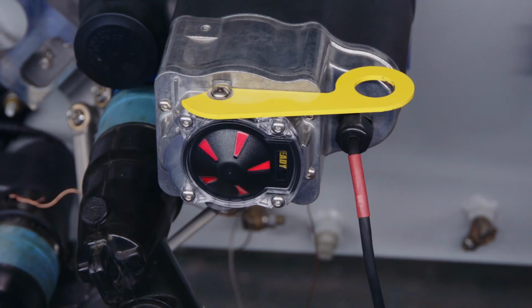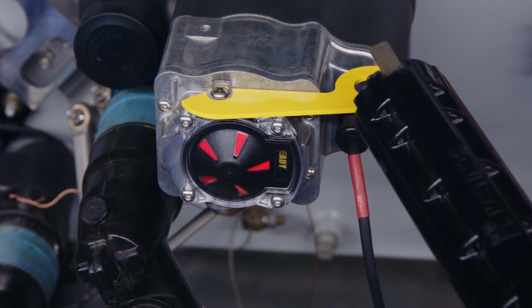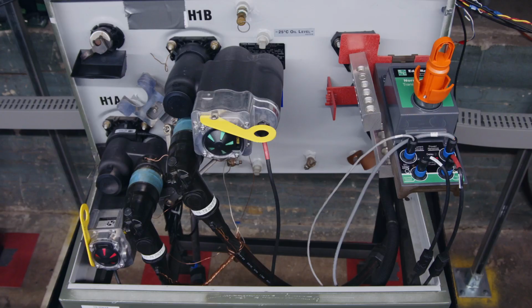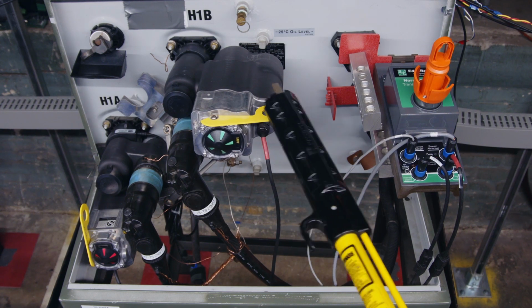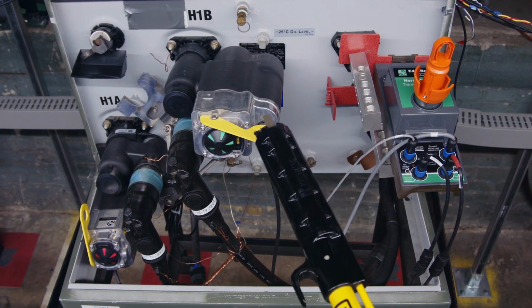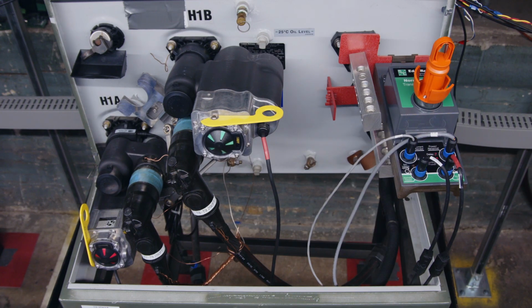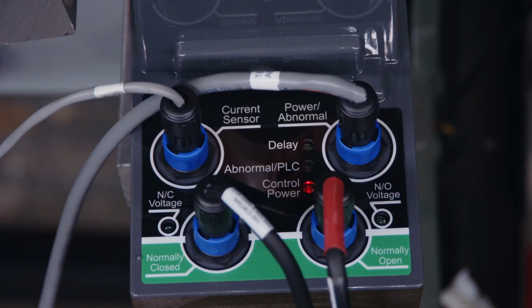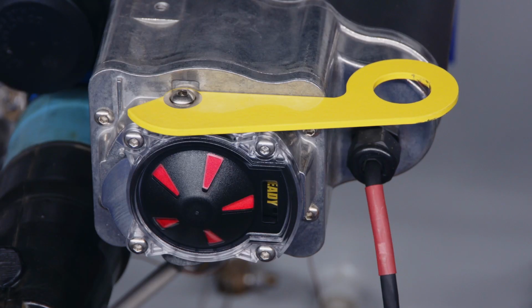Step 10. Open the H1B bushing well interrupter by pulling the yellow lever forward once. Step 11. Close the H1B bushing well interrupter by toggling the handle from the open and locked position to the ready position 3 times, ending in the ready position. Step 12. Make sure the delay LED is blinking. It will blink 10 times and then the bushing well interrupter will close. Step 13. Make sure the indicator on the bushing well interrupter is in the closed, red, and ready position.